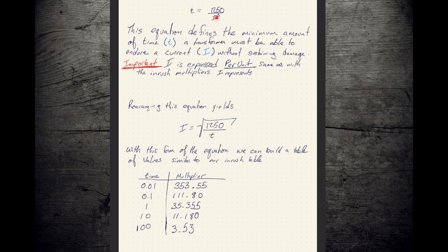So this is great if we know I. We know this formula in its current form. If we know our I, how many multiples of full load current you're exposing this transformer to, it will pop out a T. So if you're experiencing 25 times your full load current, I would expect you could solve the equation, T seconds before your transformer might suffer damage.